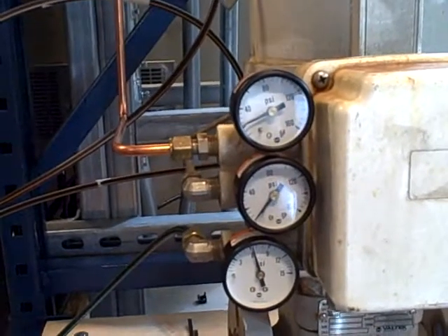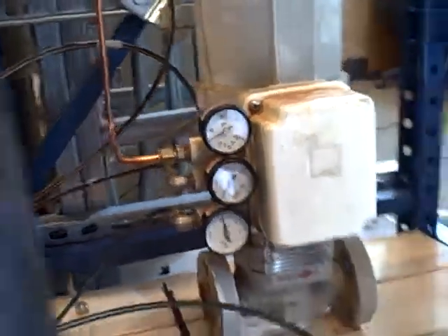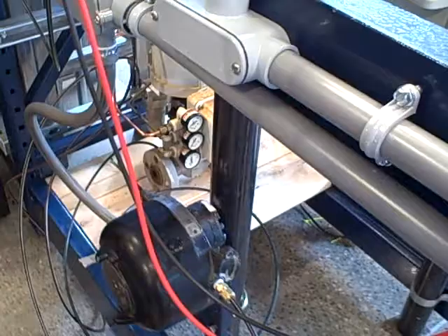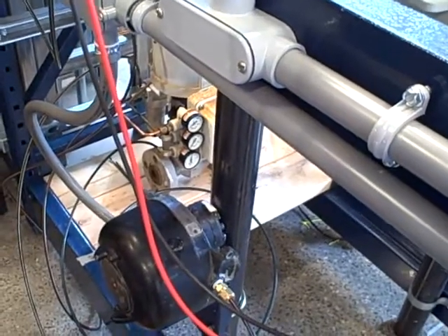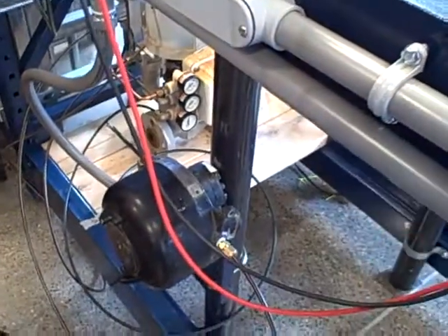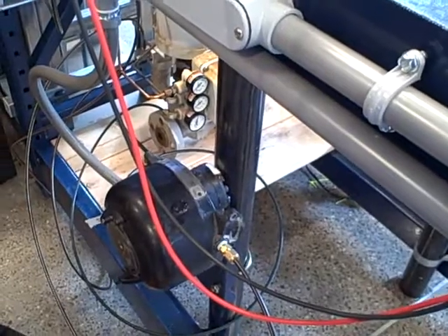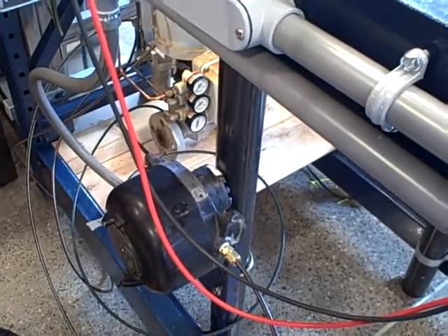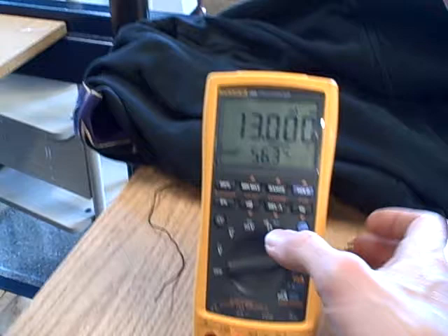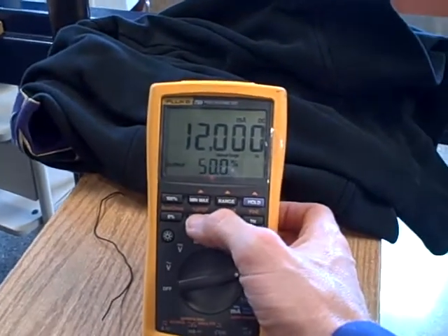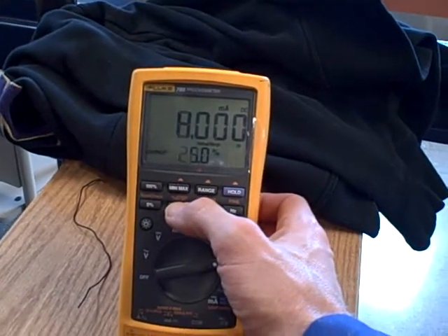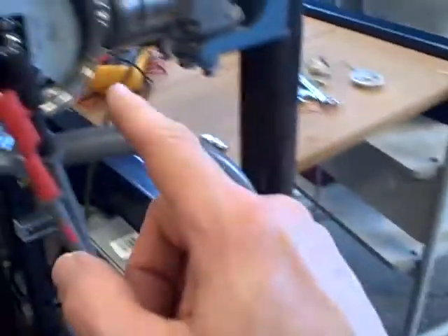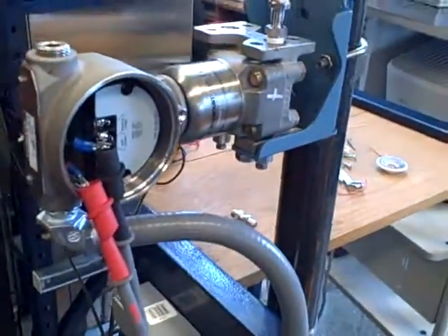Truth be known, every digital control system works like this. The only difference is how fast it scans. Some systems are slower than this, some are faster. The only controller that goes through at pretty much an infinite speed is an analog PID controller, and you don't find too many of those anymore. So, in summary, a demonstration of the Fluke Model 789 process meter and how we can use it to simulate the current that would normally be put out by a two-wire loop-powered transmitter.